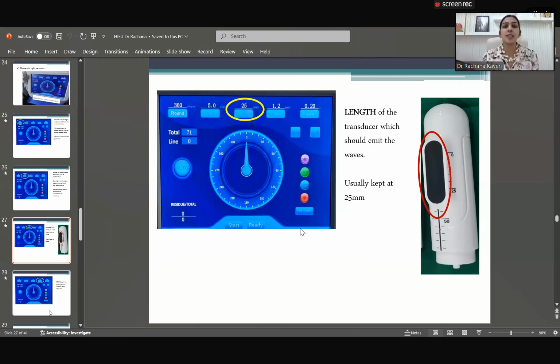Now the next parameter is the length. On the side of the screen, you can see the probe of the HIFU pictured. The black portion of this is the length of the transducer. This is basically the transducer that emits the ultrasound waves. We usually keep it at the entire 2.5 centimeter. Basically, what this means is the entire length of the transducer will be emitting the energy, and then that energy will be converged.